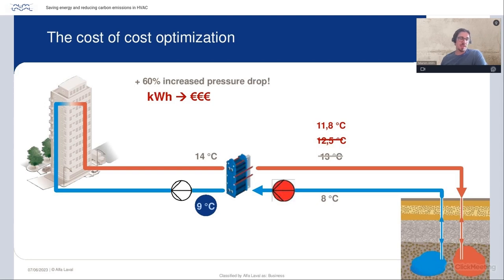And of course, increasing the flow rate, you push more water through a heat exchanger, and the price for this is the pressure drop. So the pressure drop increases quite rapidly with the flow rate through the heat exchanger.